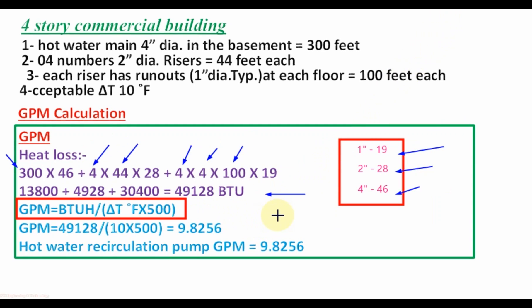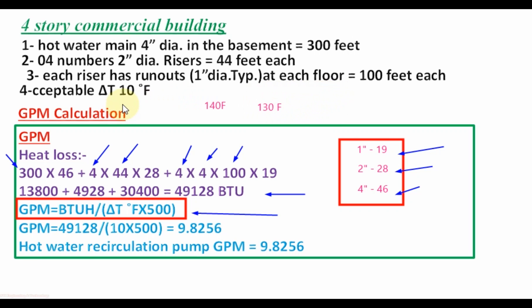For calculation of GPM we use the formula: GPM = total heat loss in BTU per hour divided by (delta T × 500). The electric water heater supplies hot water at 140°F and the required minimum temperature at the last fixture is 130°F, so the delta T value is 10°F. Applying these values — total heat loss 49,128 BTU and delta T of 10 — we get GPM equal to 9.8256. So we need a hot water recirculation pump with a flow rate of 9.8256 GPM.